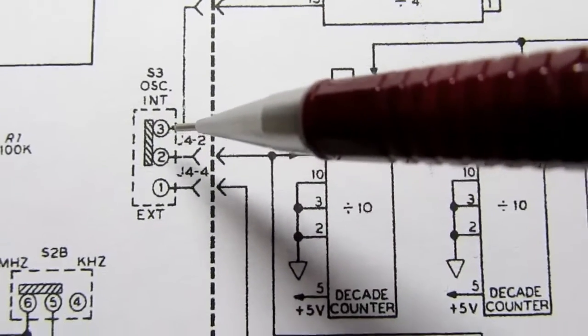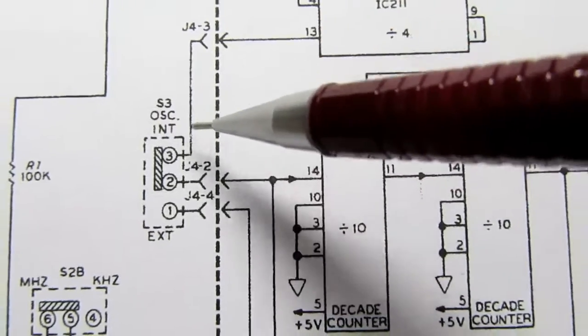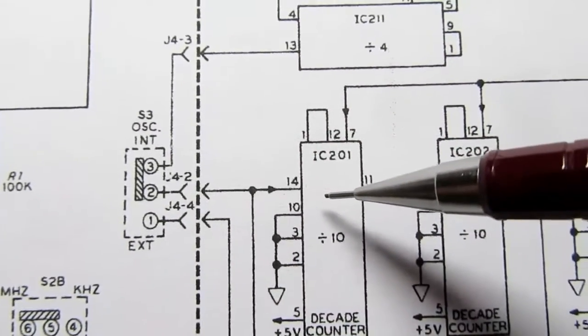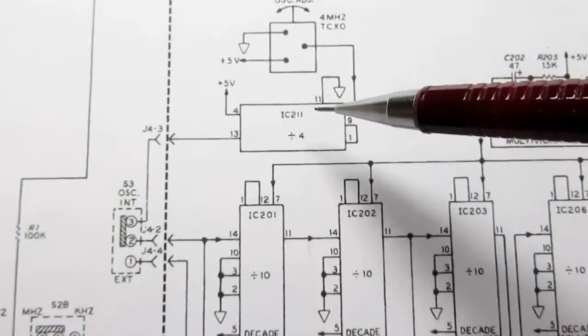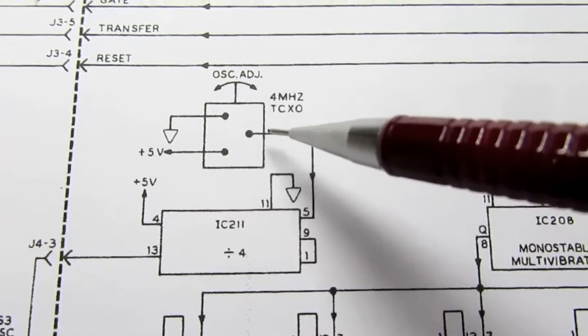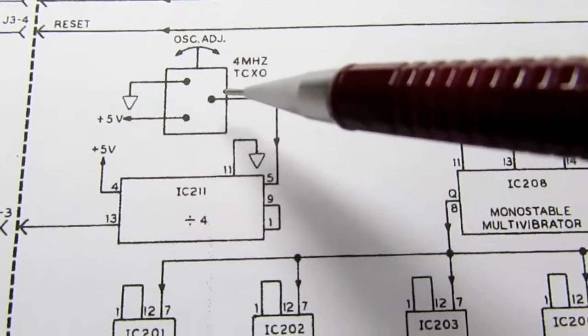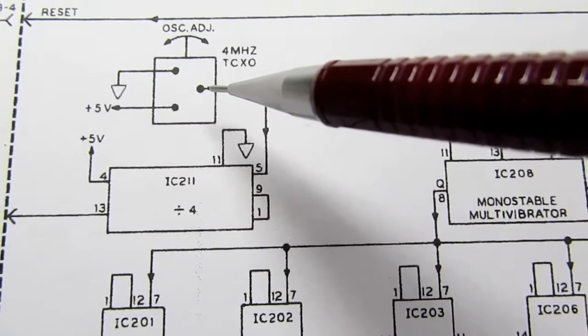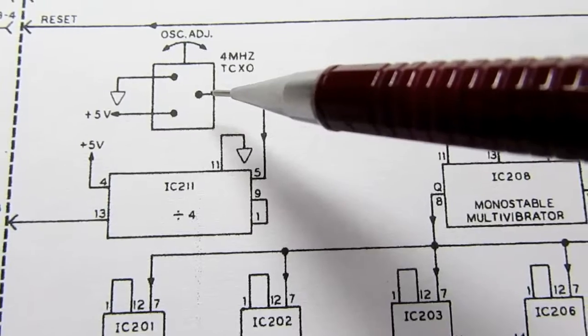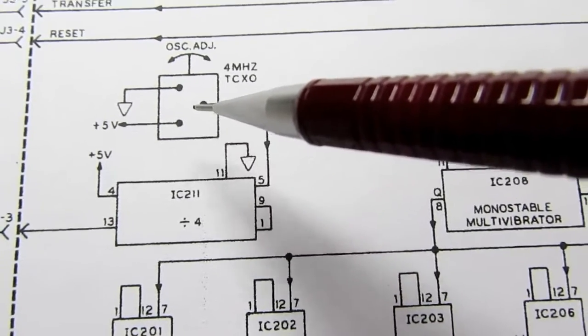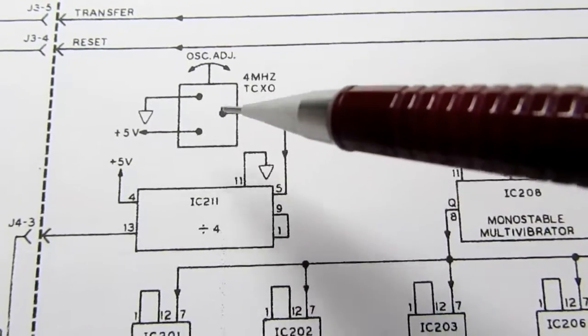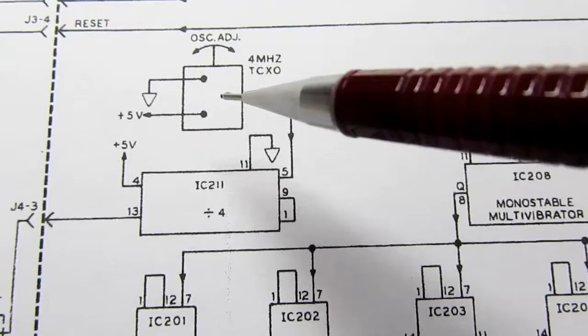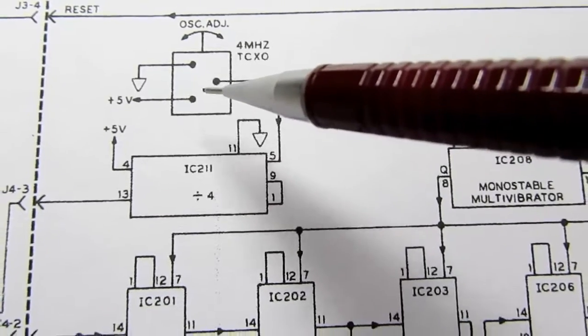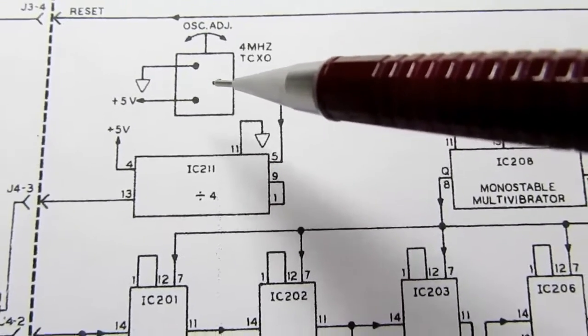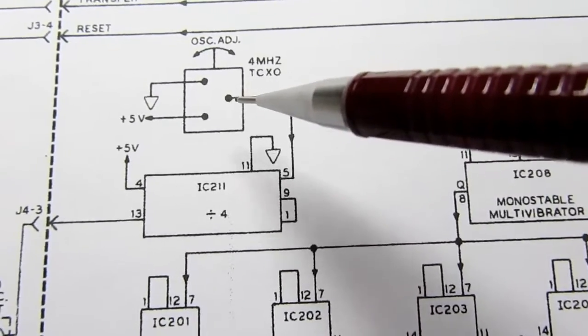And then there's a switch on the back panel where you can select to use the internal oscillator, in which case that 1 megahertz signal goes straight through and back here. On the other hand, as good as this temperature compensated oscillator is, a temperature compensated crystal oscillator is not the same as an oven, which is often called a crystal oven, where you're actually having a little heater in an insulated chamber with the crystal in it, and you're using the heater to keep the temperature at exactly the right temperature. You don't want the temperature going up and down because the crystal could change its frequency ever so slightly, so you hold it at a constant temperature. That's more expensive. This is not an oven crystal oscillator.